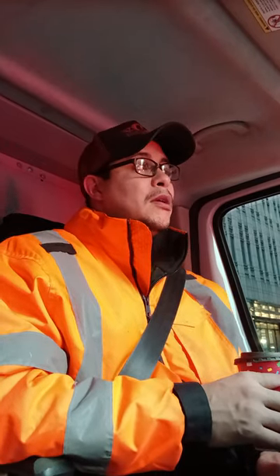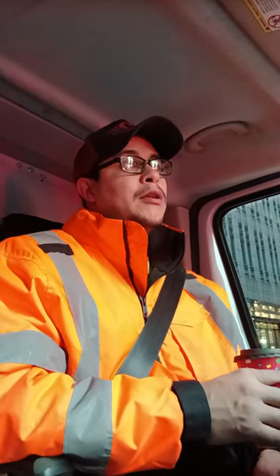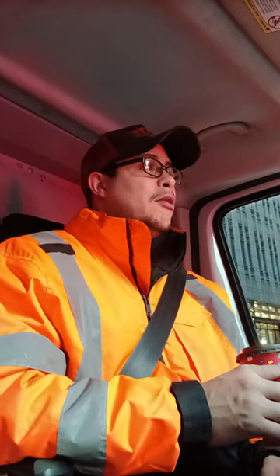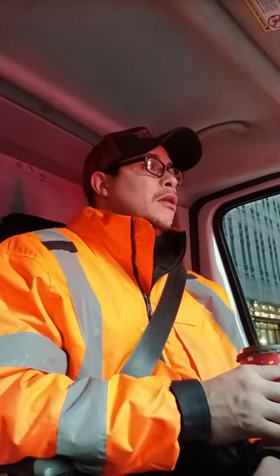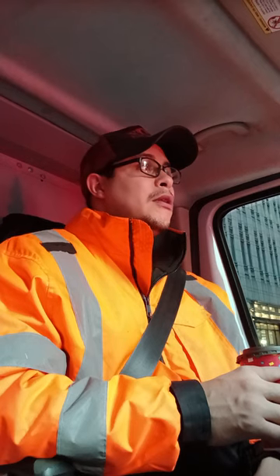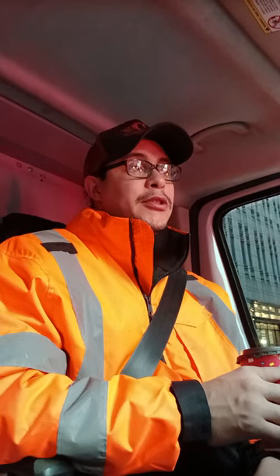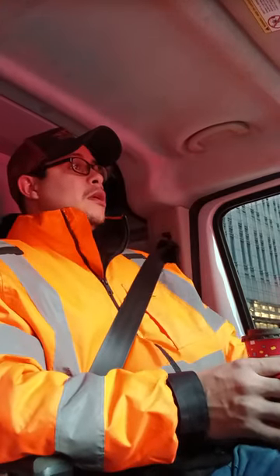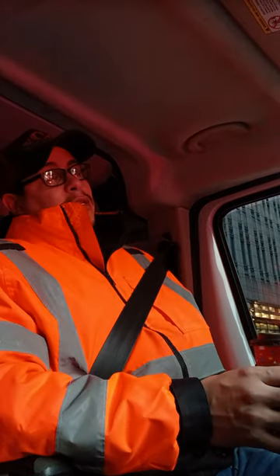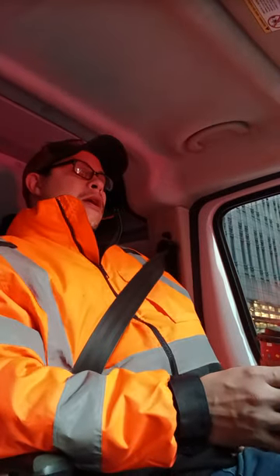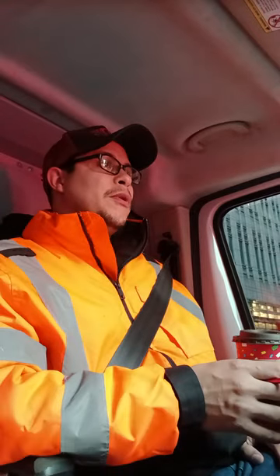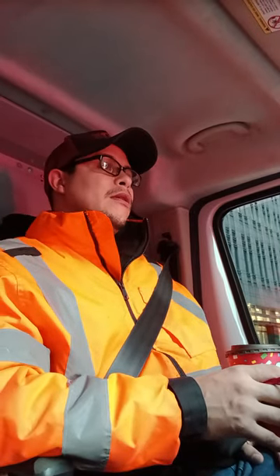They'll be tripped. Yeah, all you gotta look for is the tripped one, but they don't wanna go all the way to their basement or into another side of the apartment. So I always suggest, let's put an AFCI receptacle. So if it does trip, all you gotta do is walk across a few feet and boom, reset it. I find it more convenient and simple, easy. You don't got to walk back all the way to the circuit breaker.